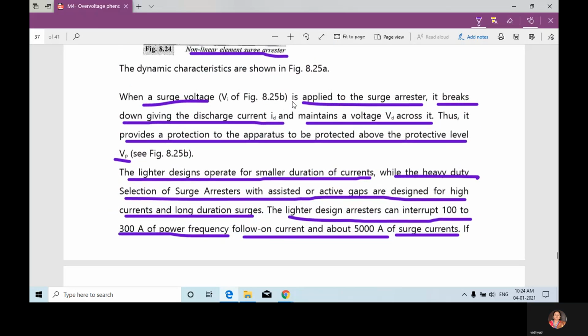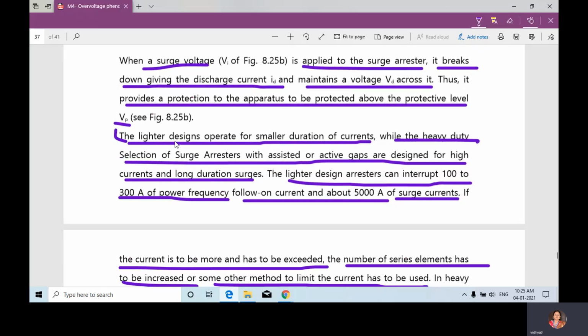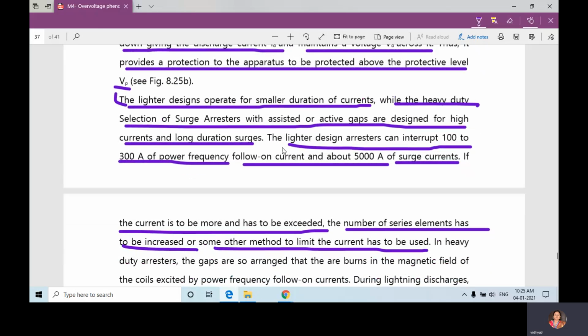Next, you need to know that when we apply a surge voltage, the surge arrestor will break down, giving the discharge current and maintaining voltage across it. It will provide protection to the apparatus to be protected, above the protective level. With a lighter design, it will operate for a smaller duration of current. If it is heavy duty, it will operate for high currents and for a long duration. The lighter design arrestor can interrupt 100 to 300.